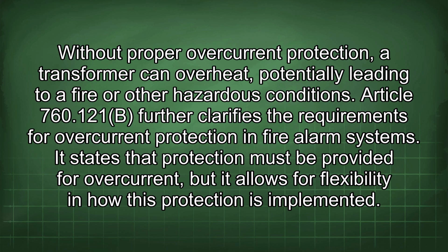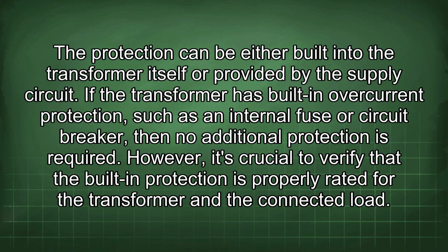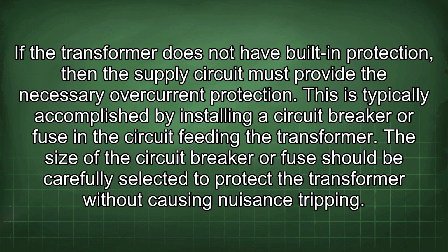It states that protection must be provided for overcurrent, but it allows for flexibility in how this protection is implemented. The protection can be either built into the transformer itself or provided by the supply circuit. If the transformer has built-in overcurrent protection, such as an internal fuse or circuit breaker, then no additional protection is required. However, it's crucial to verify that the built-in protection is properly rated for the transformer and the connected load. If the transformer does not have built-in protection, then the supply circuit must provide the necessary overcurrent protection.